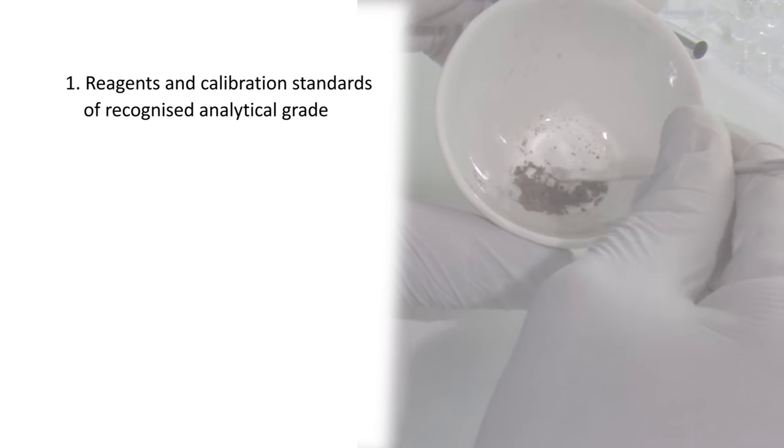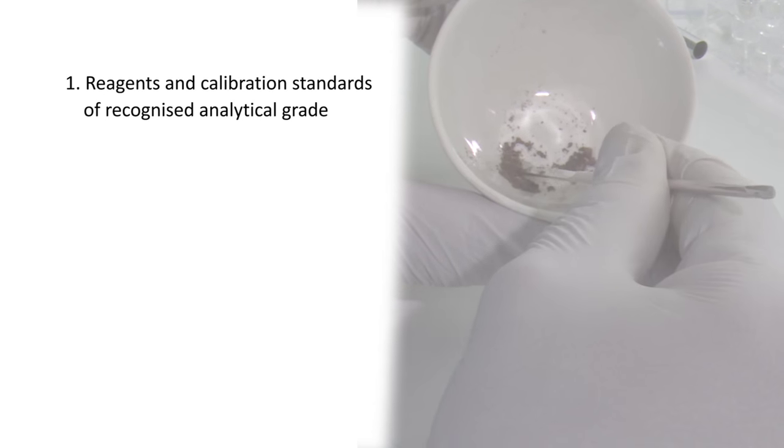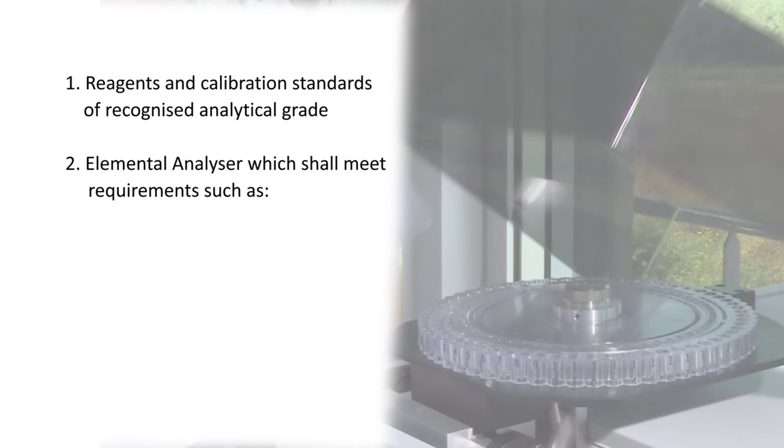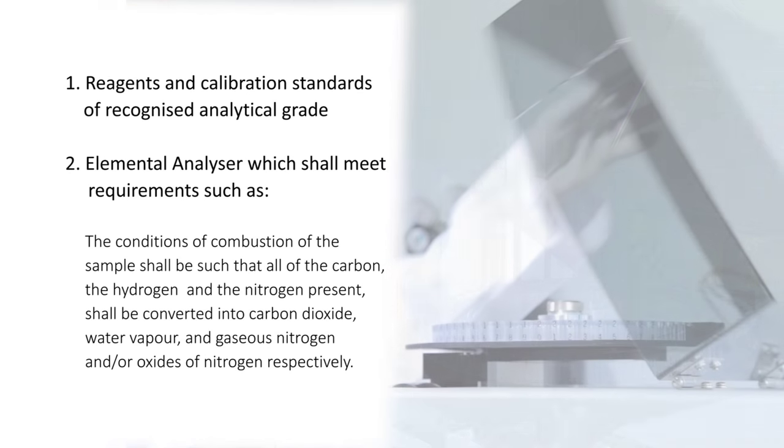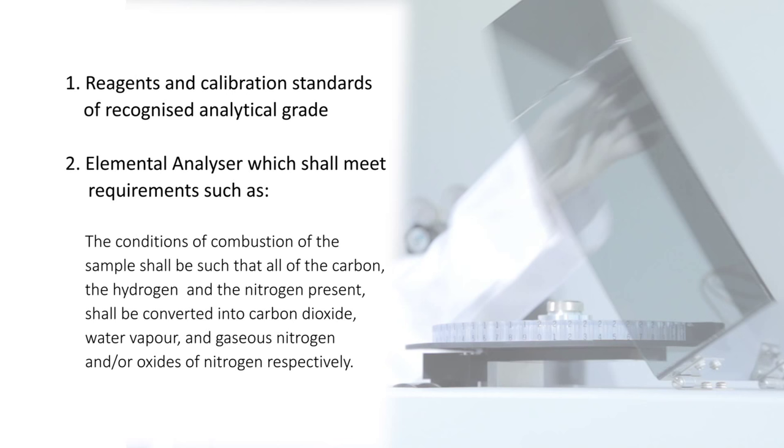The required equipment and reagents for the implementation of the test are reagents and calibration standards of recognized analytical grade, and an elemental analyzer which shall meet requirements such as: the conditions of combustion of the sample shall be such that all of the carbon, the hydrogen, and the nitrogen present shall be converted into carbon dioxide, water vapor, and gaseous nitrogen and/or oxides of nitrogen respectively.